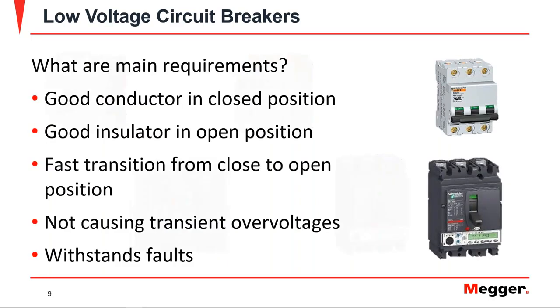So now that we know what a circuit breaker is, what are the main requirements? What do we expect from a circuit breaker when it's installed in the system? First of all, it has to be a very good conductor when it's in the closed position, when our system is under normal circumstances. In other words, contact resistance will be very low, or as low as possible. It has to be a good conductor under normal conditions.